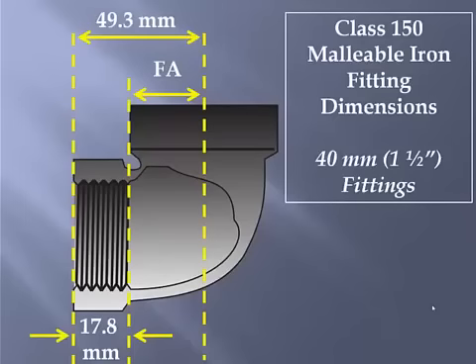What the pipe trades worker will be required to calculate is the fitting allowance when given the face-to-center and thread engagement for any specific fitting. Once you subtract the thread engagement from the face-to-center dimension, the result will be the fitting allowance. In this case, 31.5 millimeters.